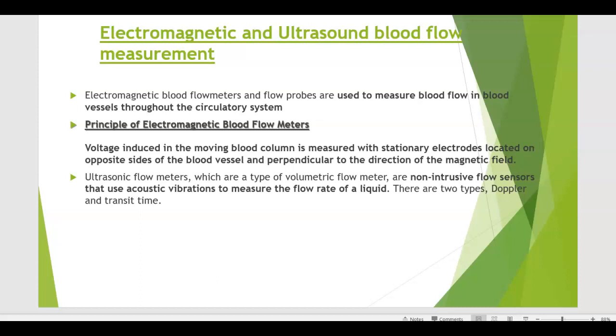Electromagnetic and ultrasound blood flow measurement. Electromagnetic blood flow meters and flow probes are used to measure blood flow in blood vessels through the circulatory system. The principle of electromagnetic blood flow meters is that voltage induced in the moving blood column is measured with stationary electrodes located on opposite sides of the blood vessel and perpendicular to the direction of the magnetic field.